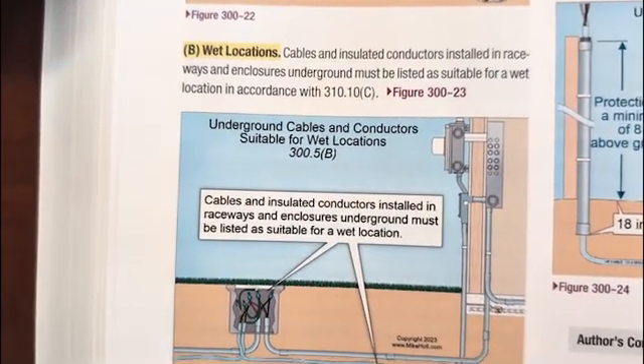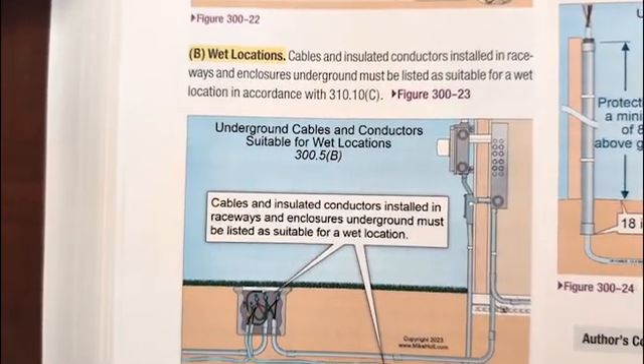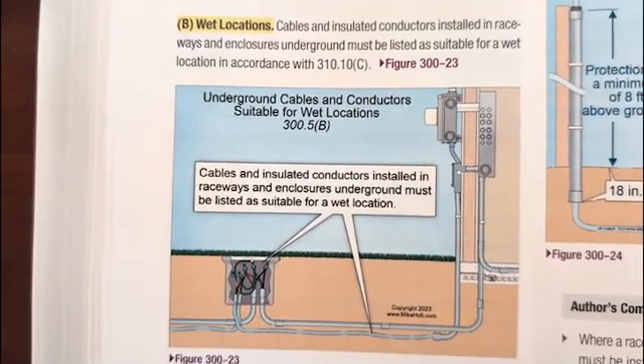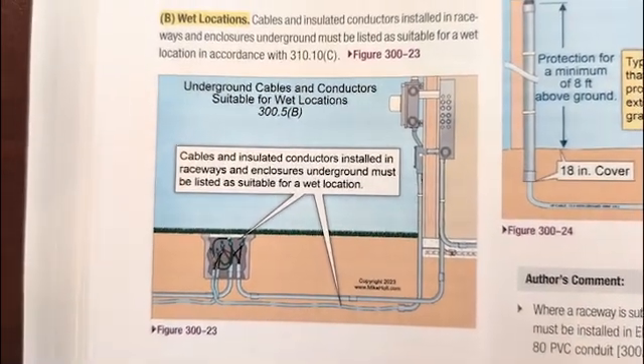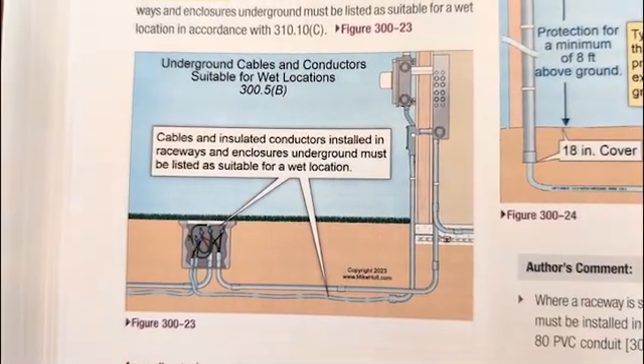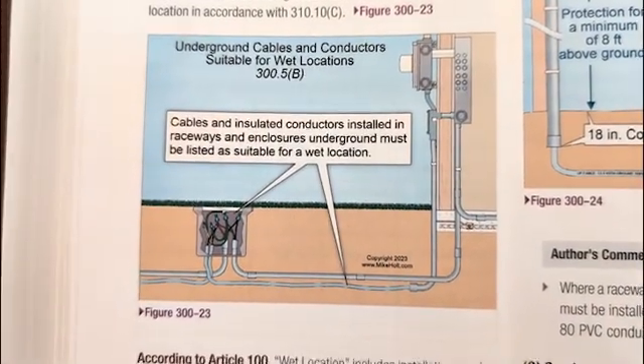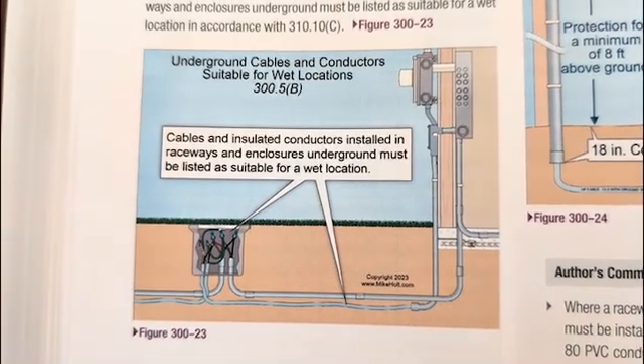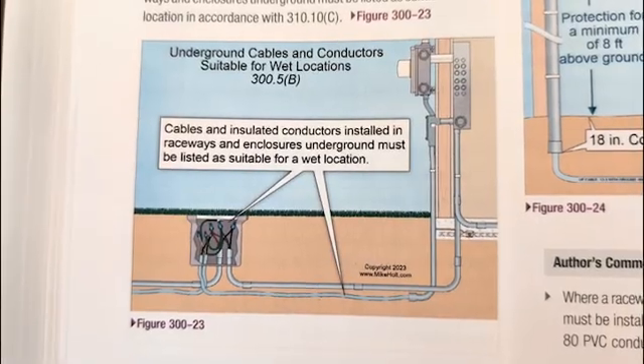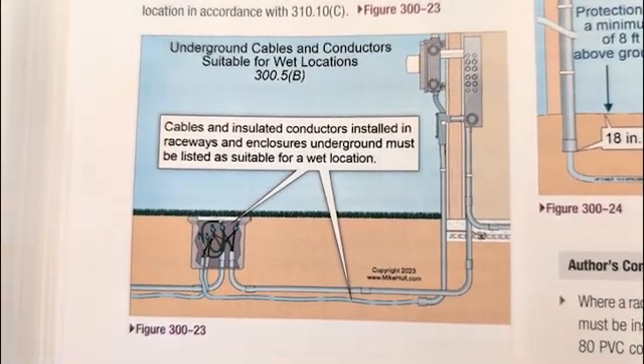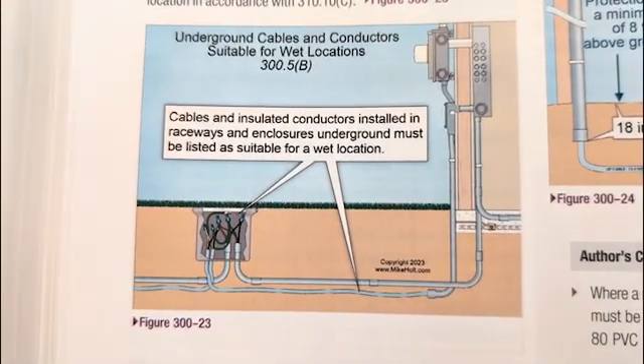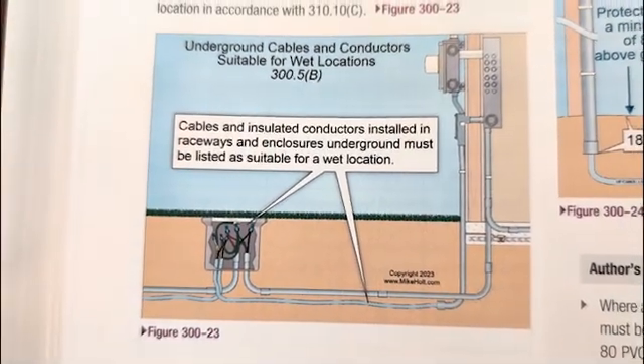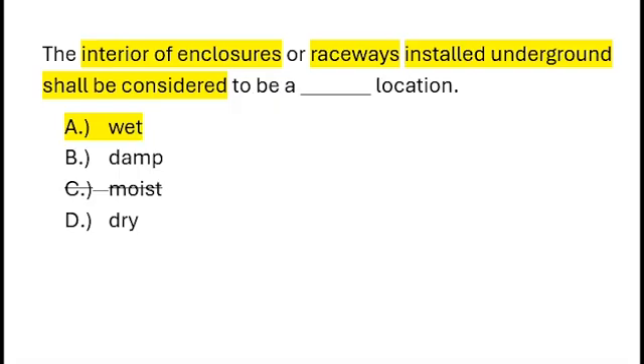Looking at 300.5(B) — wet locations — cables and insulated conductors installed in raceways or enclosures underground must be listed as suitable for wet locations in accordance with 310.10(C). So you can see that the enclosure interior must be rated for a wet location, as well as the conduit itself — the raceway. The interior of enclosures or raceways installed underground shall be considered to be a wet location.